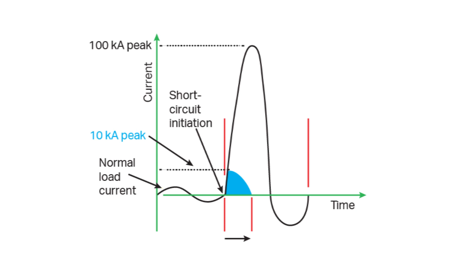If not limited, destructive faults can reach levels of 30,000 amps or higher, even up to 200,000 amps in the first half cycle, which is approximately 8 milliseconds. The immense heat that can be produced in circuit components can cause conductor insulation damage or violent component explosions. At the same time, huge magnetic forces developed between conductors can crack insulators and destroy bracing structures, with the maximum mechanical force exerted being proportional to the square of the instantaneous peak current. It is extremely important that overcurrent protective devices limit fault currents before they reach their full potential.